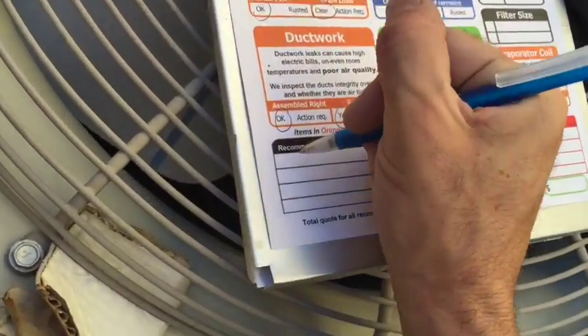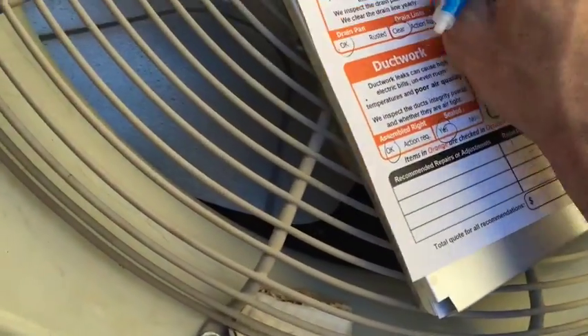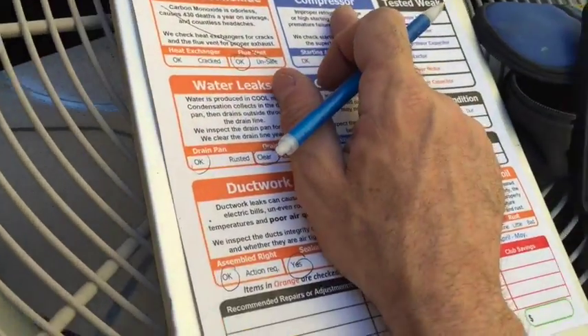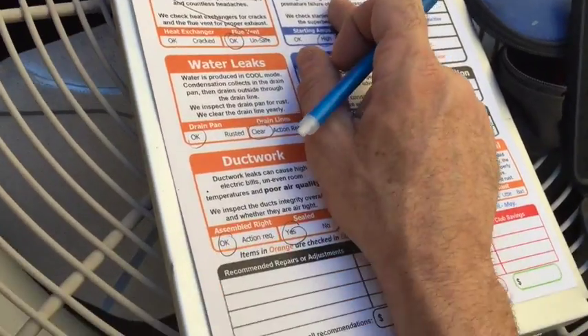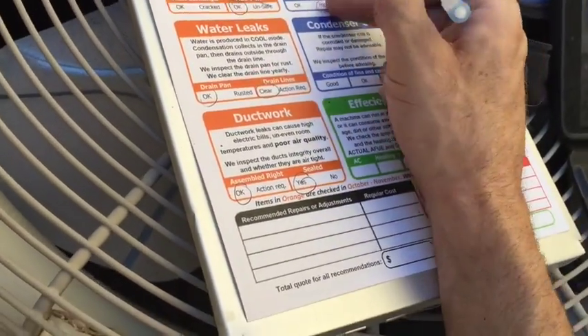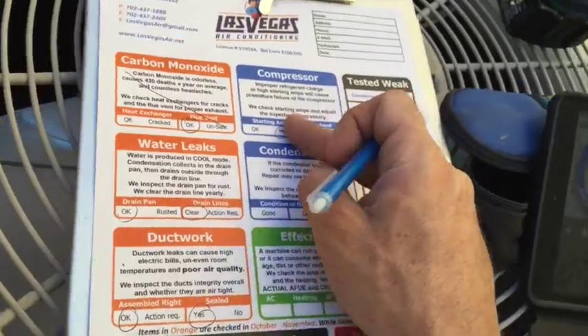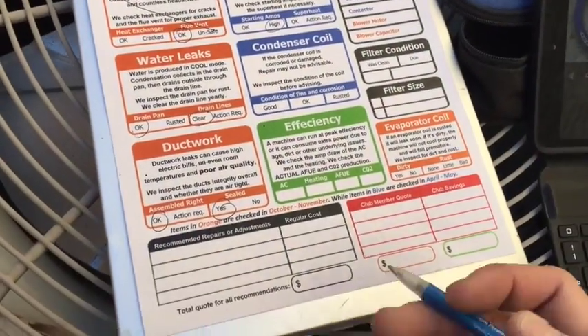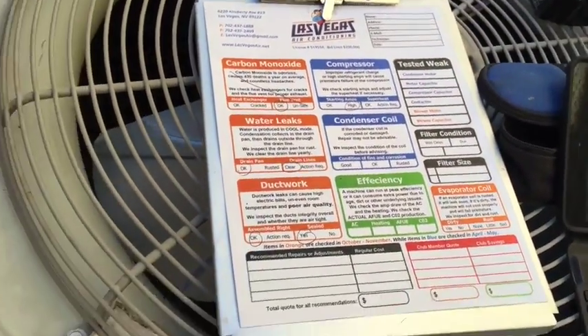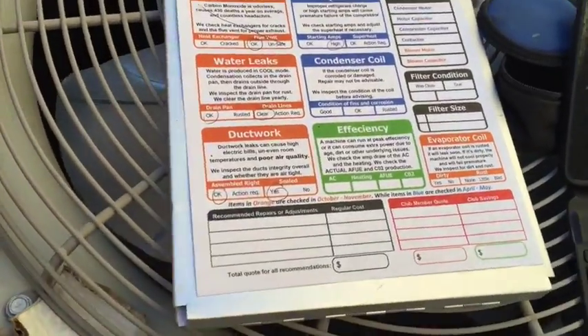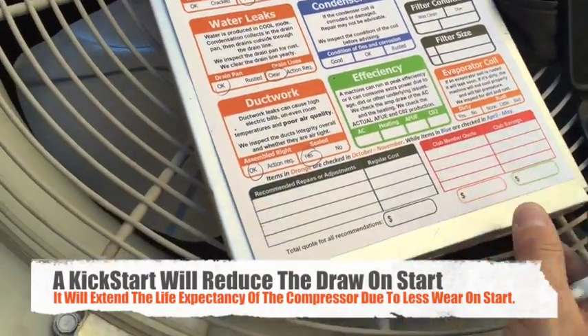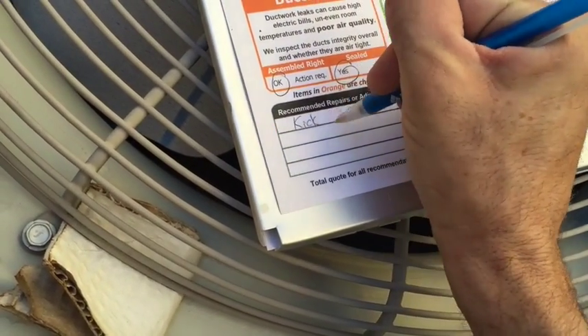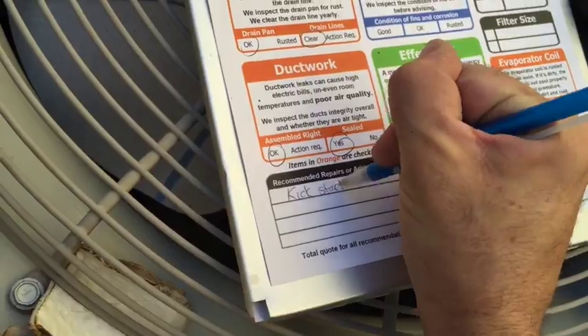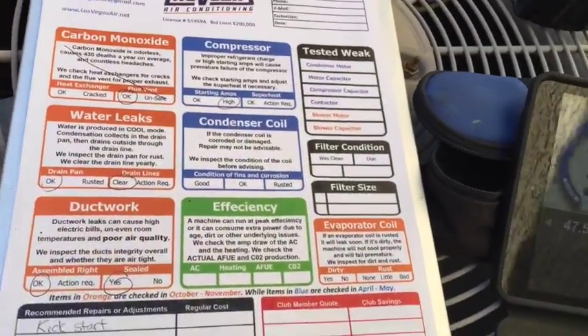So to make sure that compressor doesn't take more damage, because high starting amps will take your compressor out prematurely if left untouched. When you have a compressor pulling high starting amps, you can either do nothing, or you can install a kickstart kit to prevent that high draw in the beginning. So a kickstart would make this system last longer.